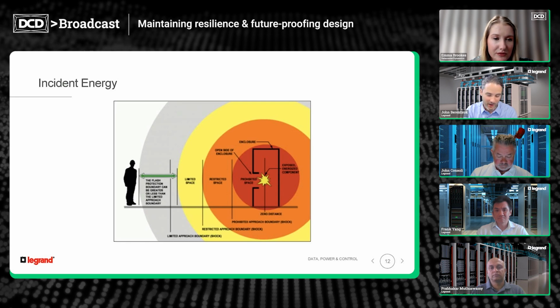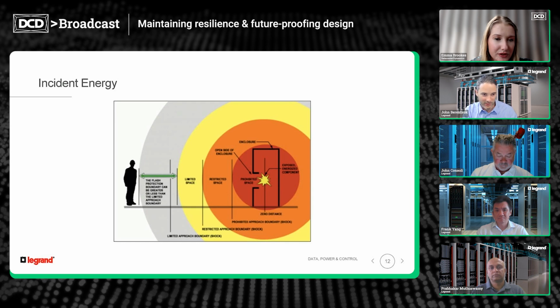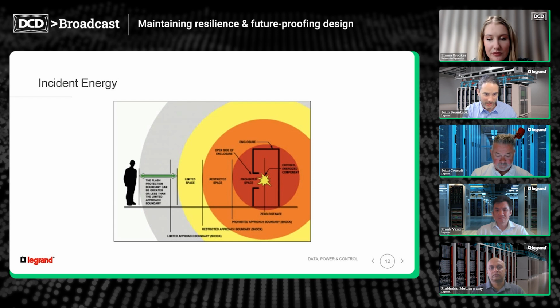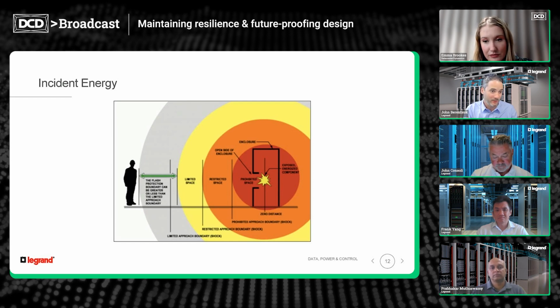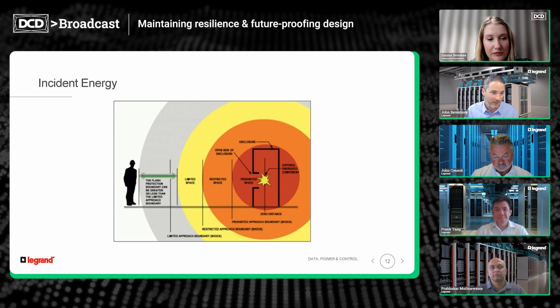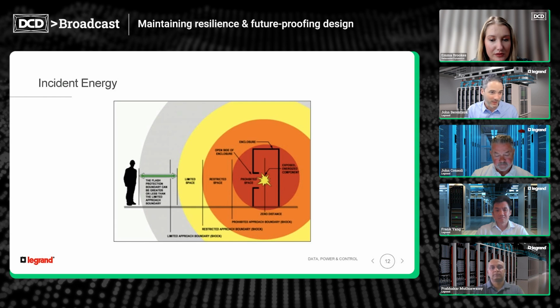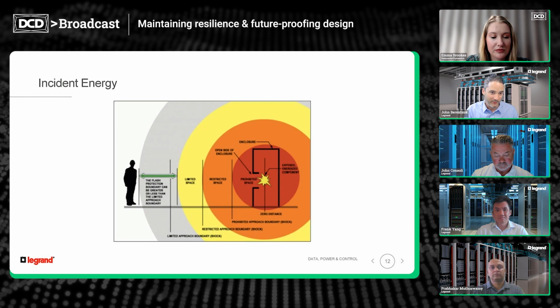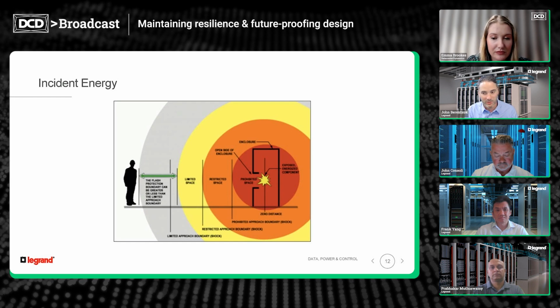Voltages are a lot higher than they used to be. When we started, the racks were 3 kilowatts, and on the West Coast you had people in flip-flops and board shorts plugging in equipment, which was about as safe as plugging into your outlet. Fast forward to today where you have 480-volt power rails and 65 kA fault currents, it's quite a different situation.